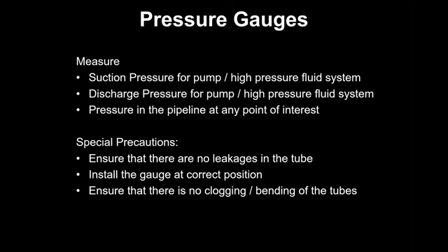Like we use it in a power plant. It is very common to find out the pressure drop in a condenser, because that is the heart of the power plant. If the condenser is clogged and the pressure drop is higher, the flow is less. Correspondingly, you won't get the vacuum, the heat rate will go up, and ultimately turbine performance will drop. So pressure drop measurement becomes critical. So is the pump performance. For that, pressure gauges are used.